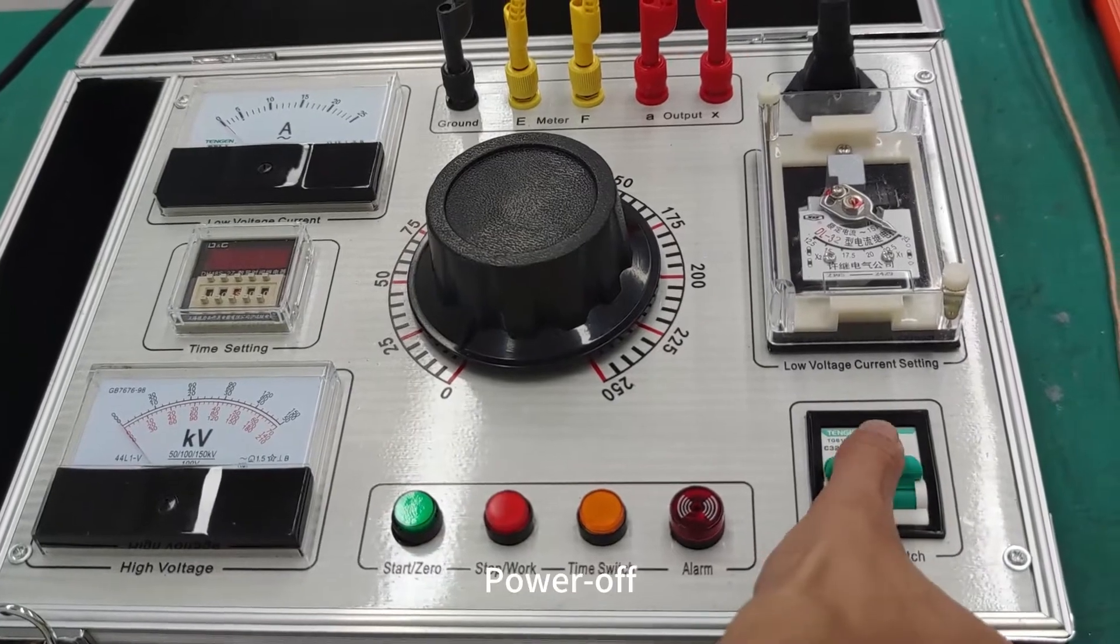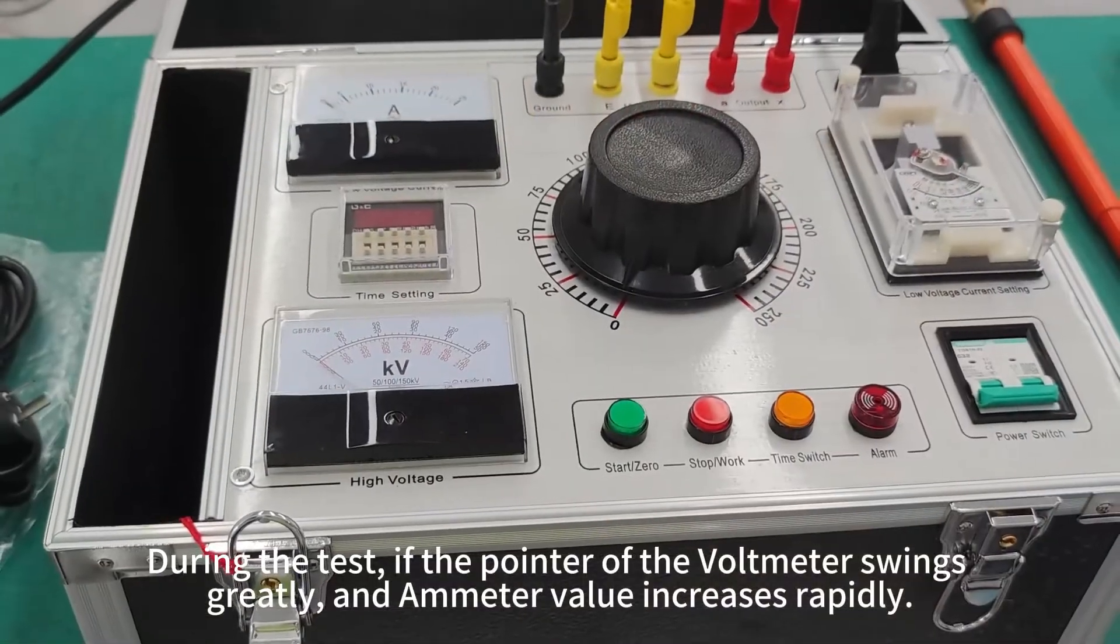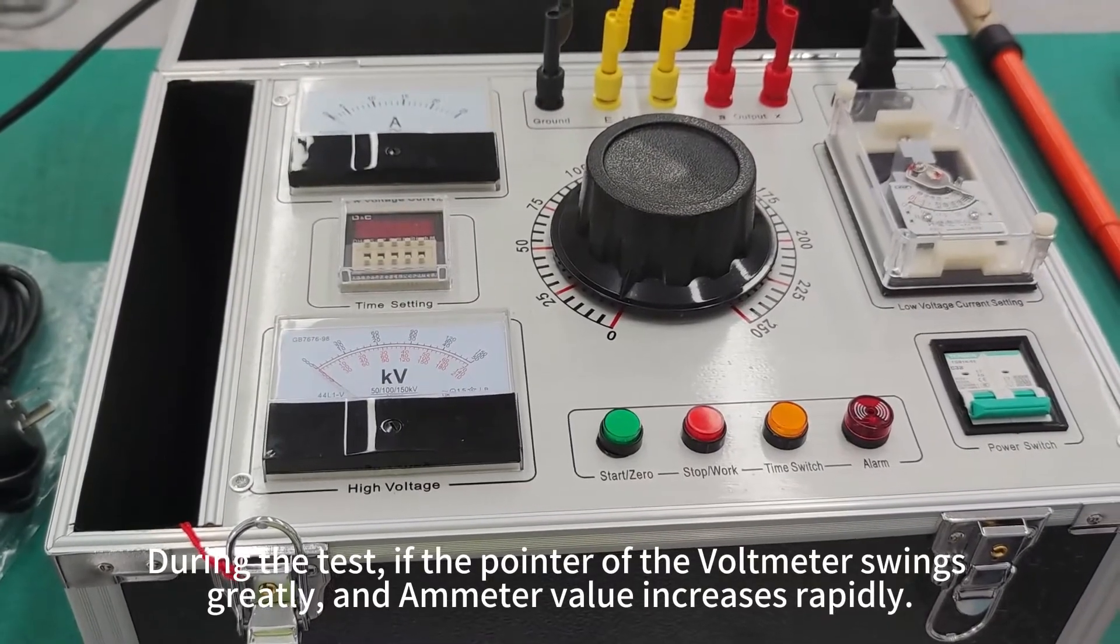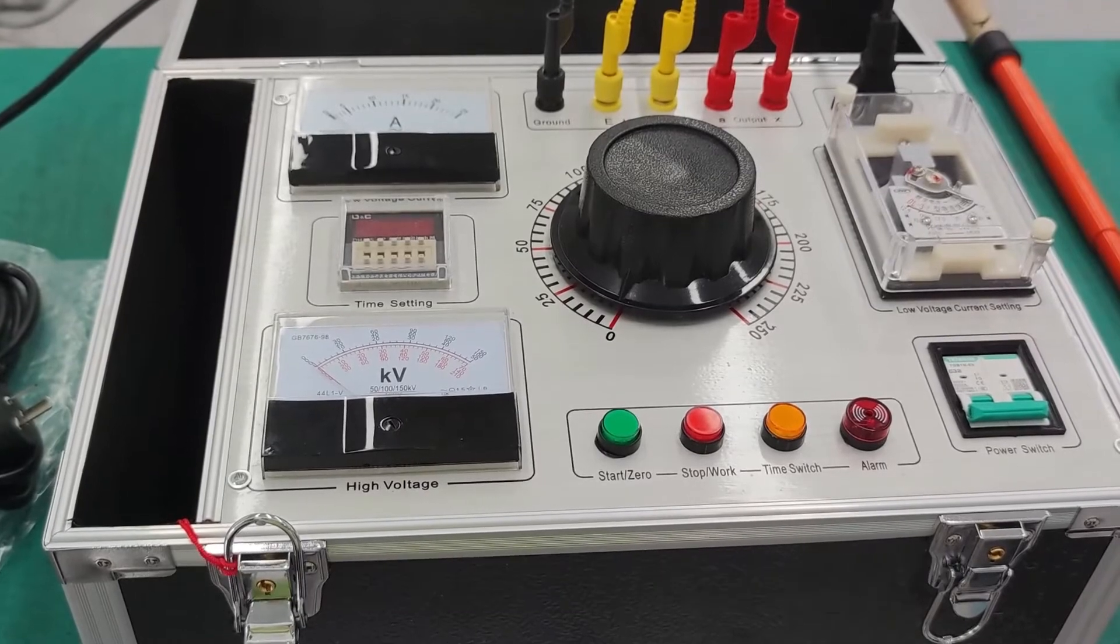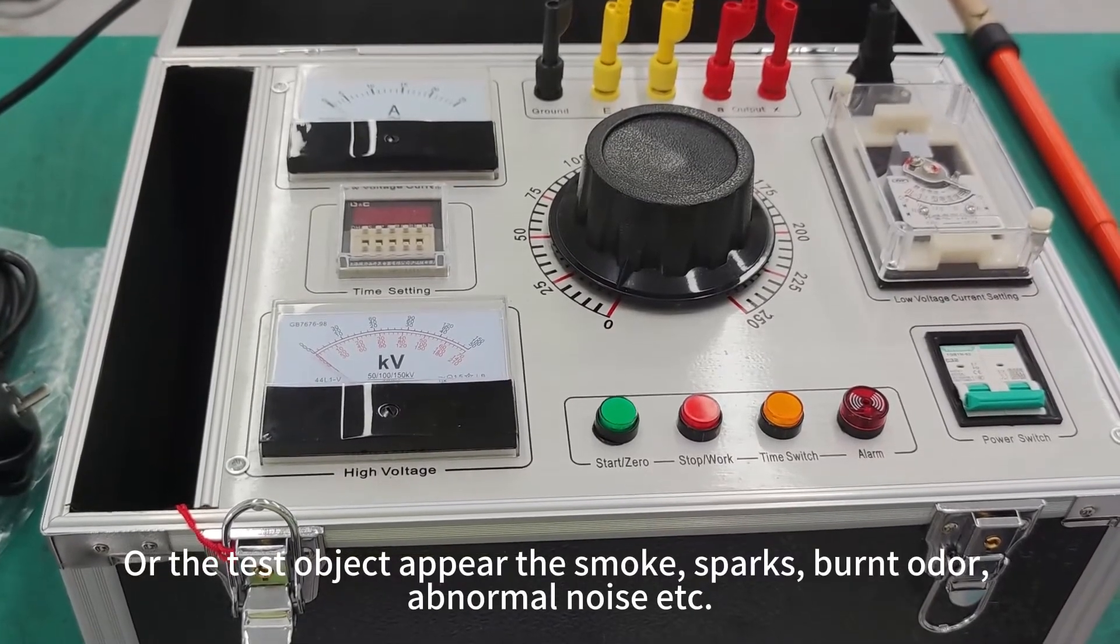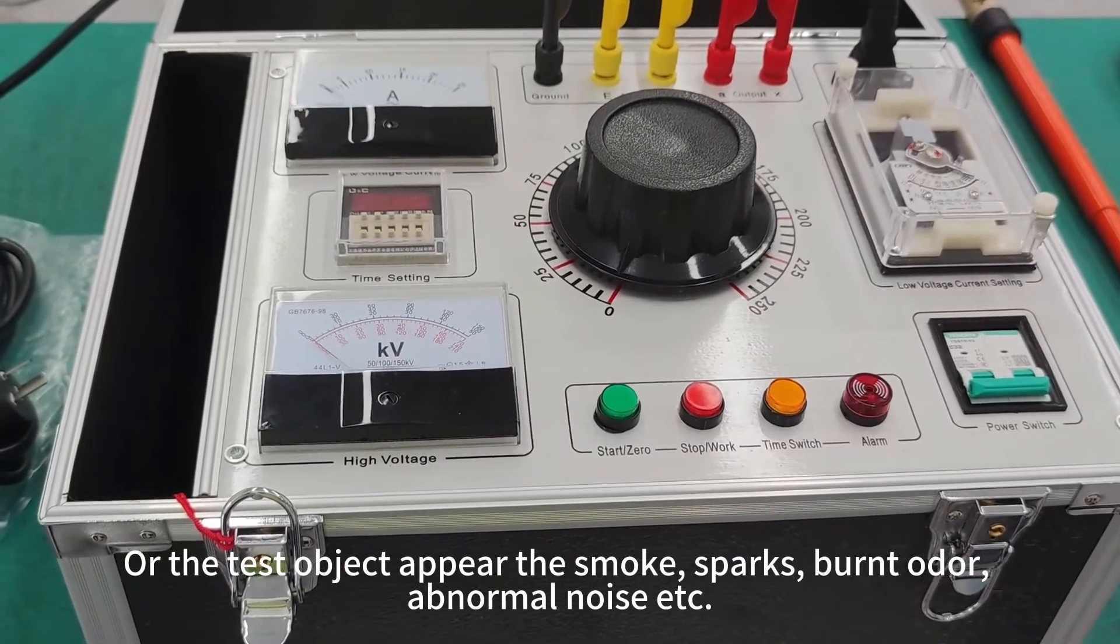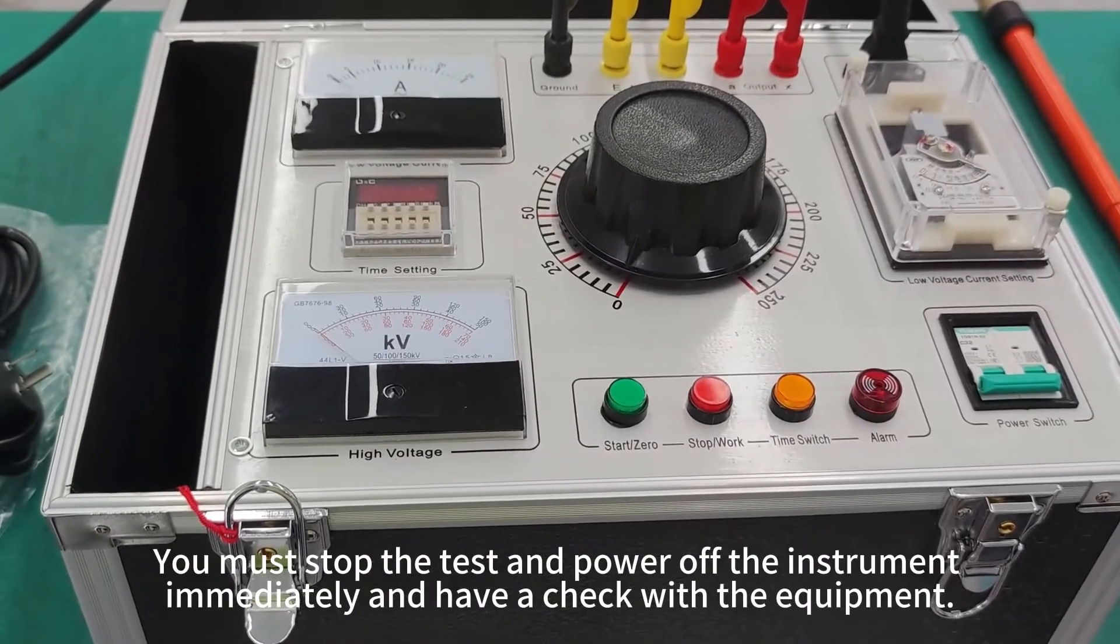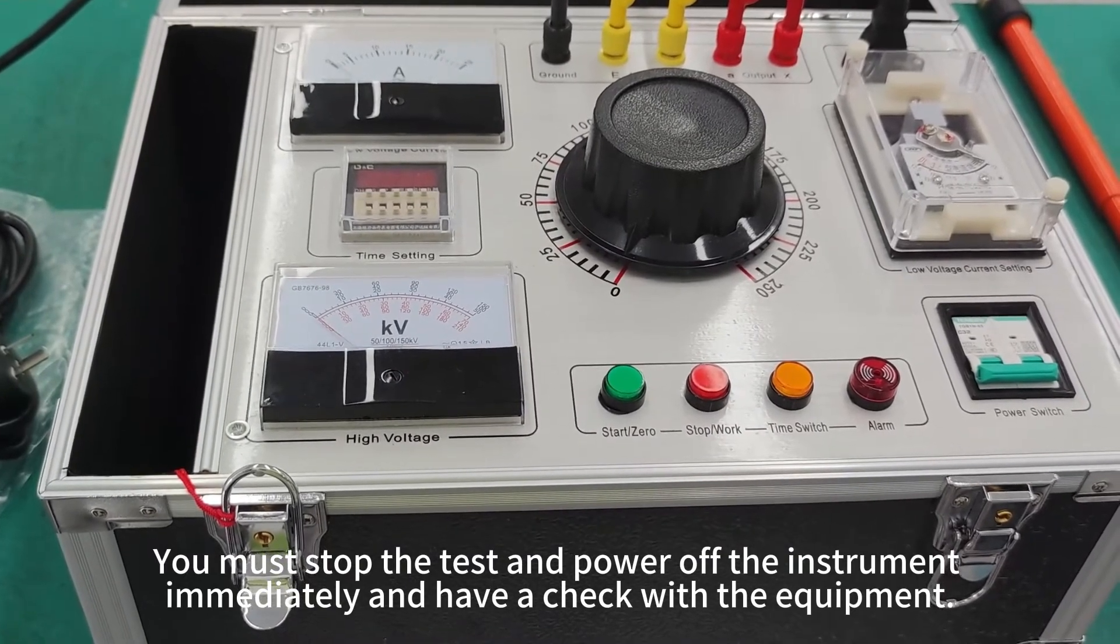Power off. If the pointer of the voltmeter is swinging greatly and ammeter value increases rapidly, or the test object appears smoke, sparks, burnt odor, or abnormal noise, you must stop the test and power off the instrument immediately and check the equipment.